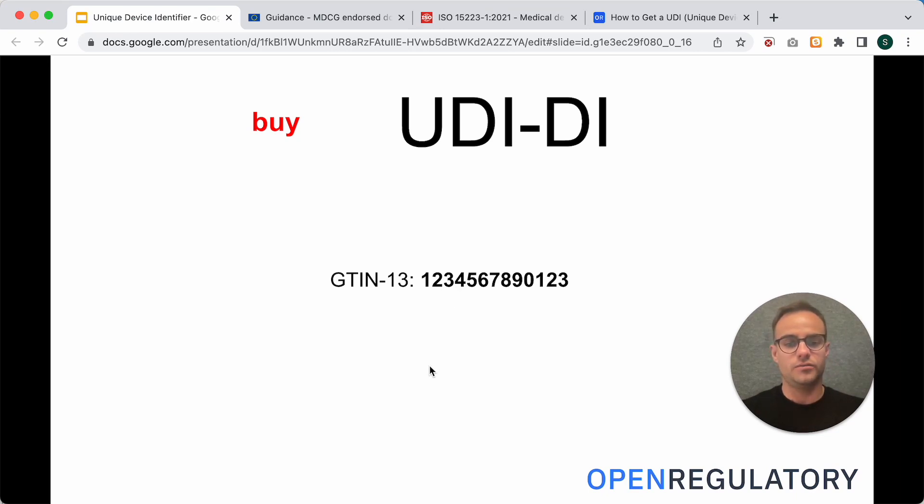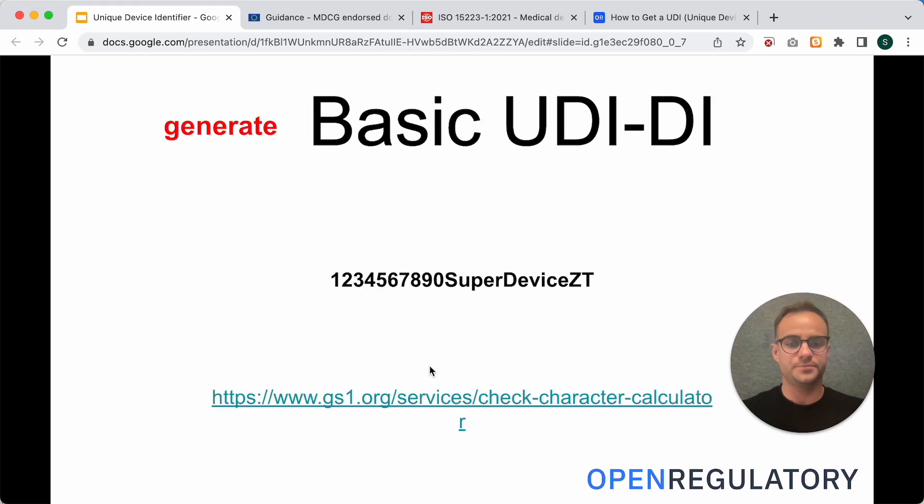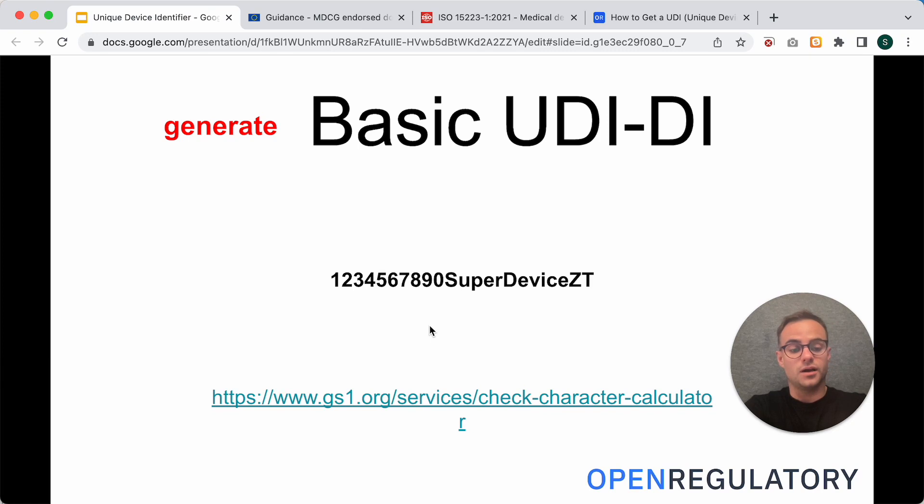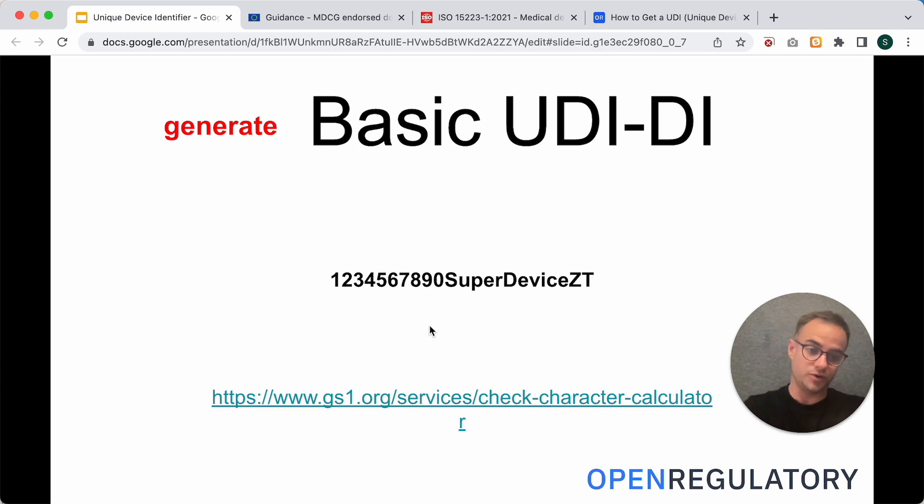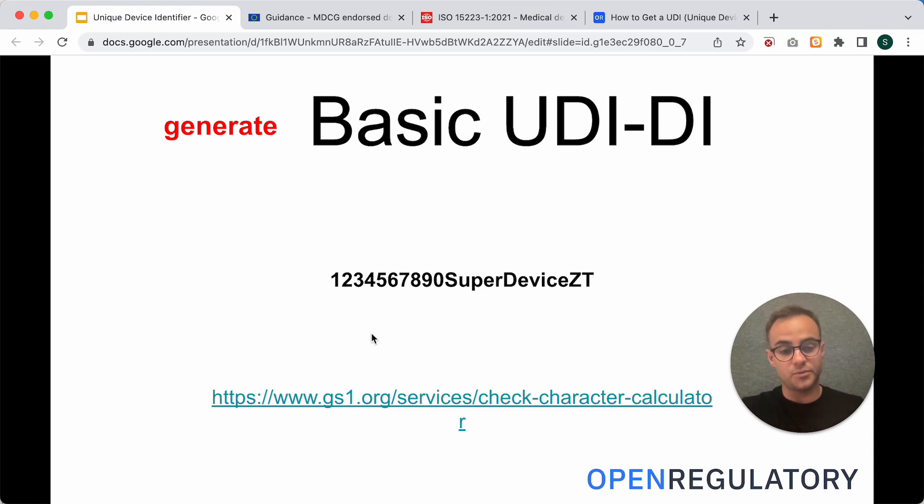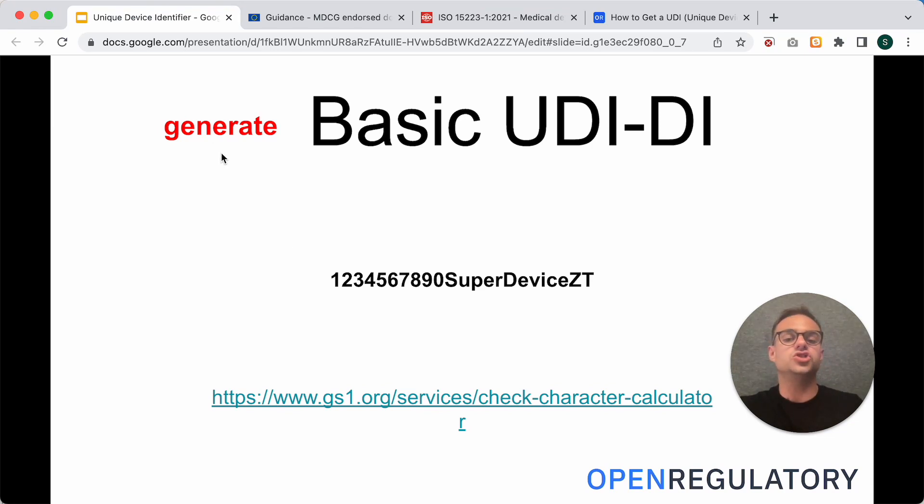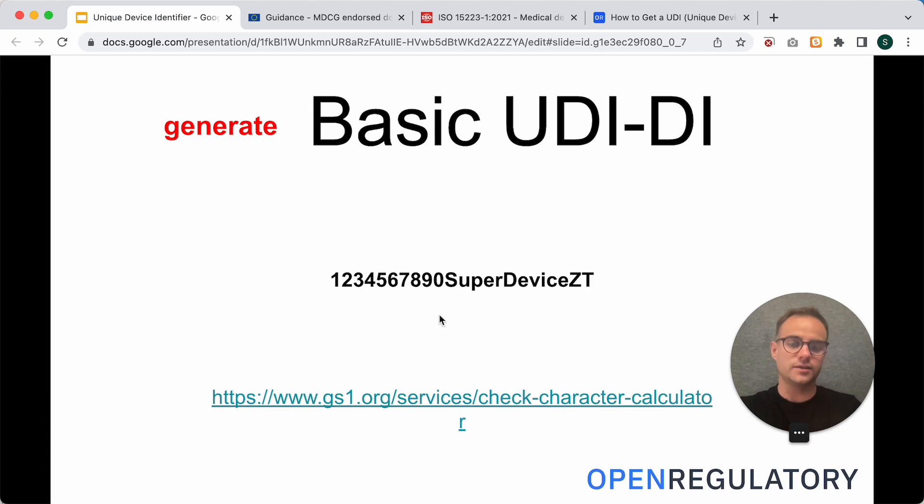All right. Now, when you bought this UDI-DI, you will get a so-called company prefix along with it. And with this number, that's unique for your company, you can generate your basic UDI-DI. The basic UDI-DI looks something like this. I will show you how to generate it at the example of GS1.